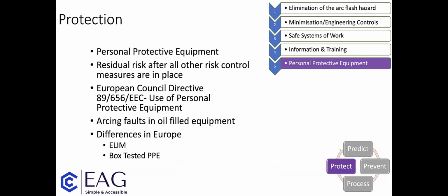Bear in mind, though, that arcing faults in oil-filled equipment, PPE won't protect you against that. And in fact, I have knowledge of people who have been killed as a result of that many years ago, but the memories are still foremost in my mind. PPE won't protect you against that, I'm afraid, the disruptive failure of oil-filled equipment. There are differences in Europe, ELIM, box tested PPE, which again is for another day.